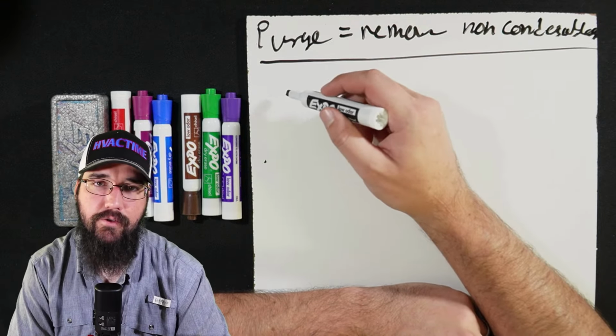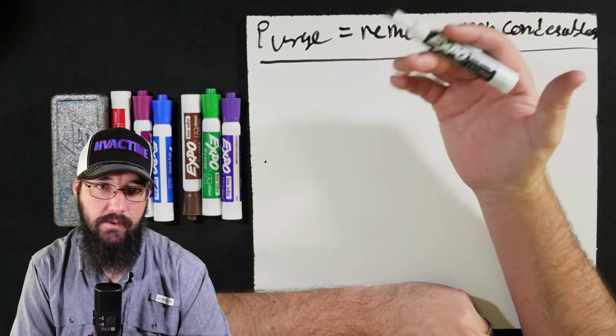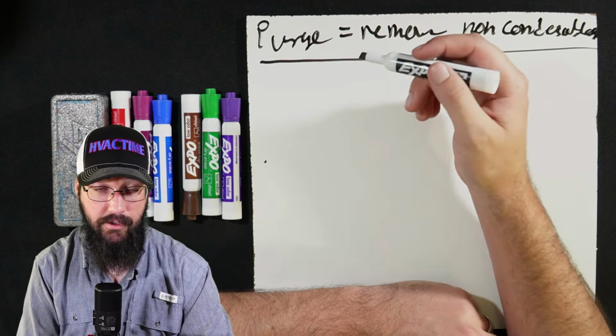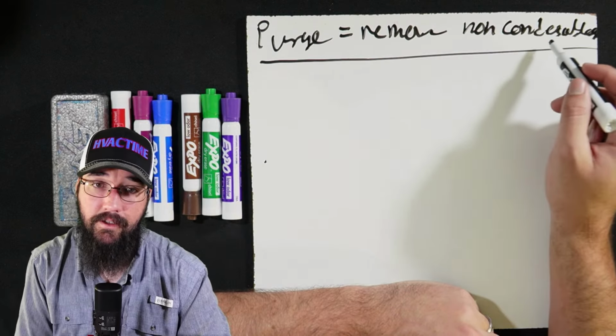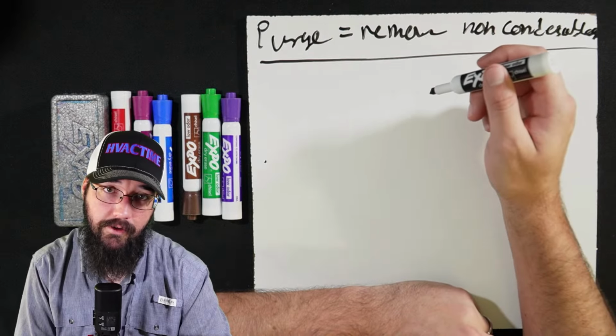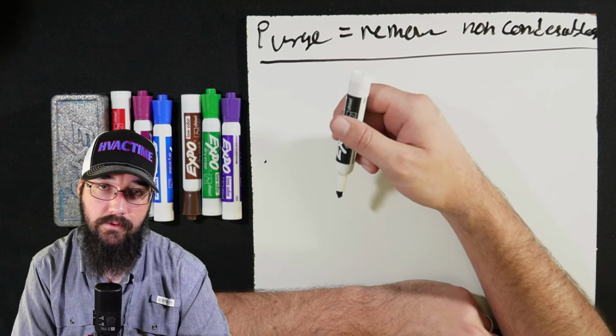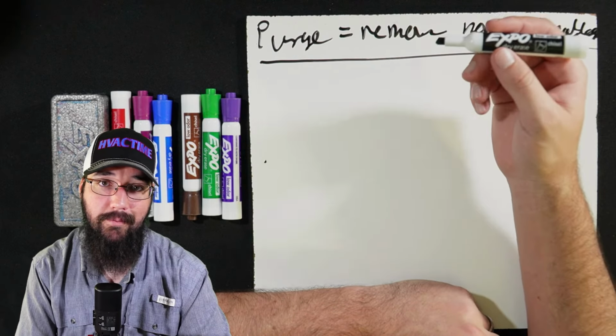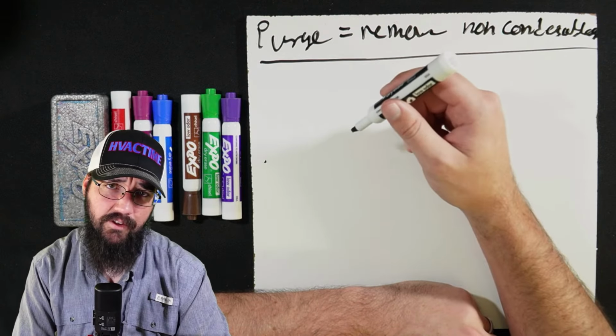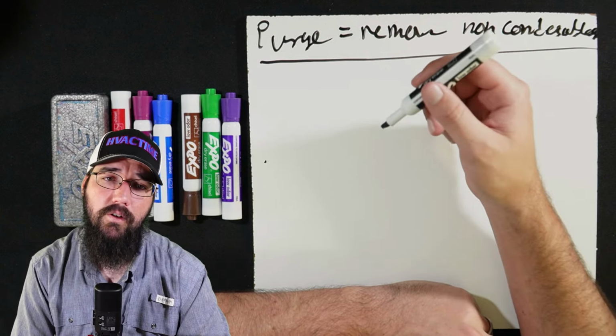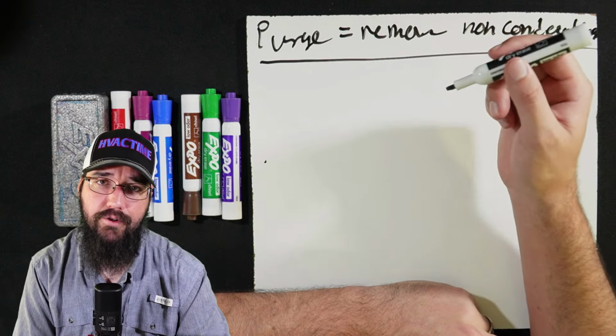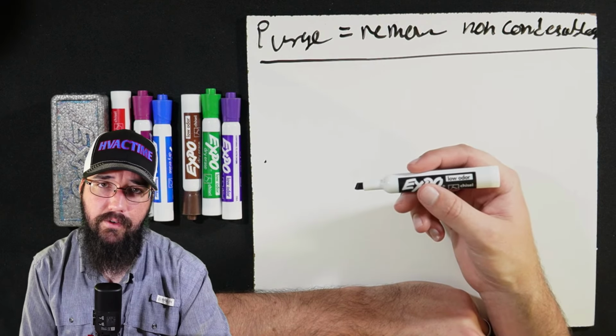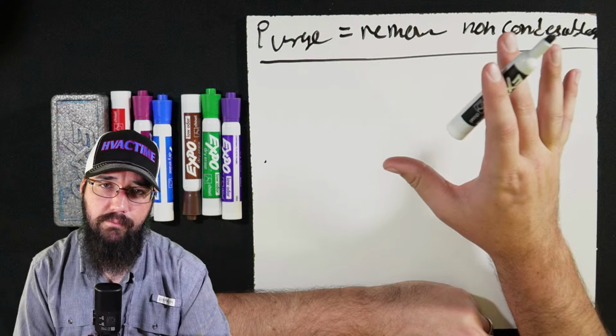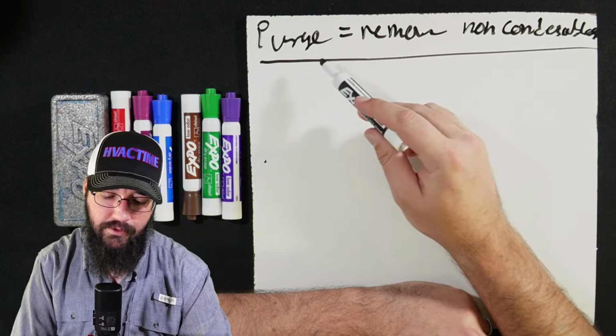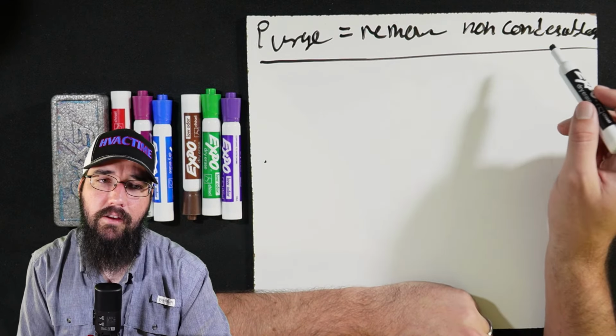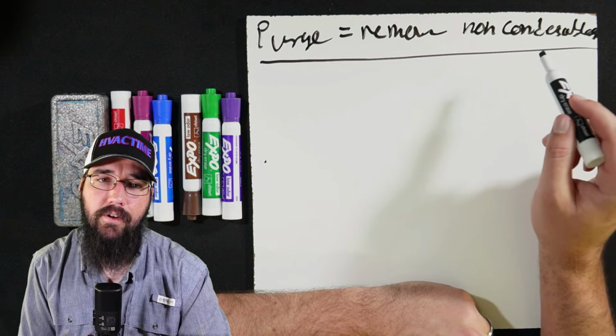So nitrogen, we all are very familiar with. It's the same stuff we use to pressurize machines. It's a non-condensable. Water, on the other hand, is a condensable. So the moisture, the humidity that gets drawn into the machine will condense in the purge unit and will flow out. Okay, I'll discuss that here in a moment, but just understand the core function of a purge unit.